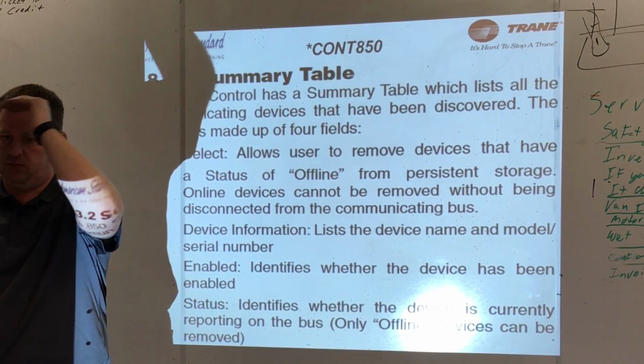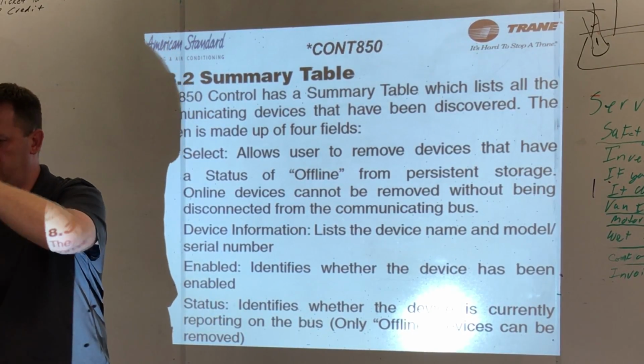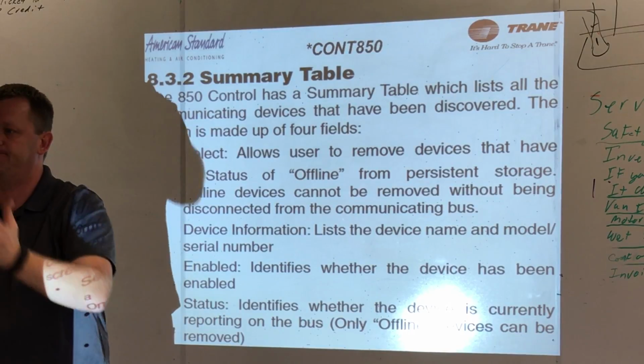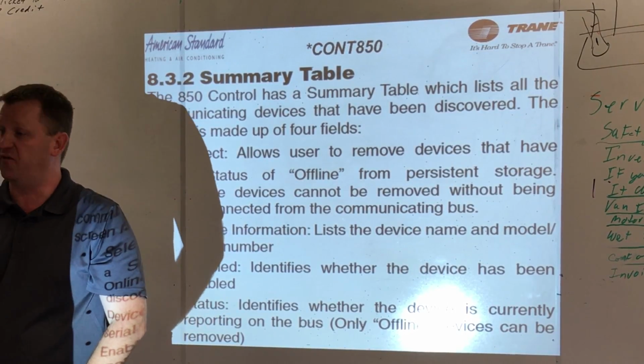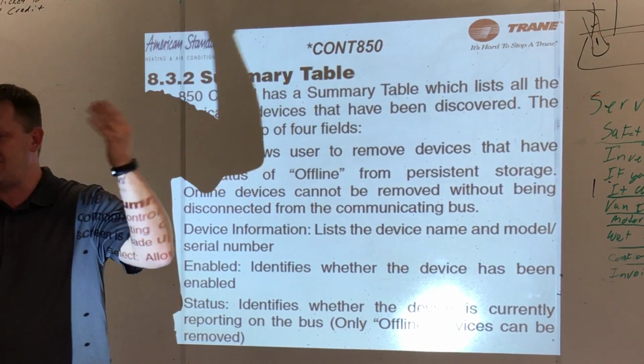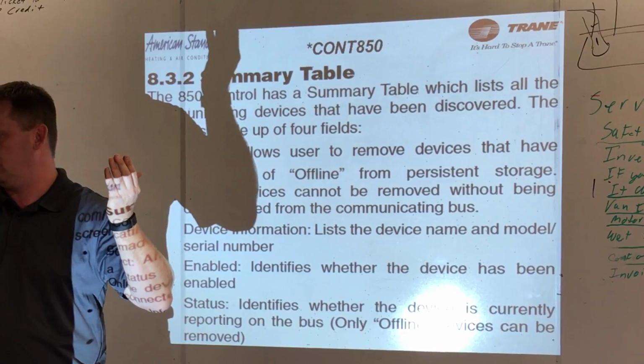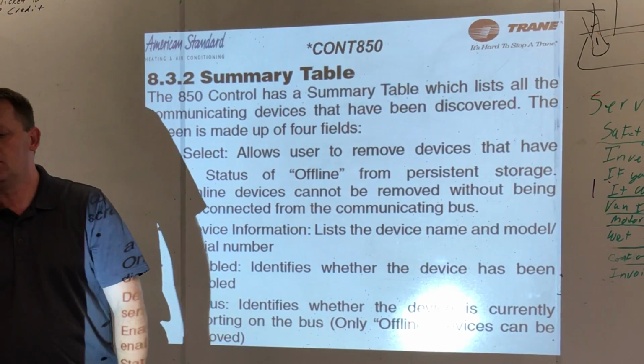Okay, you're going to go to error 126 and it's going to tell you what device is off. It'll tell you indoor unit online, outdoor unit online, Clean Effects offline. Okay, we got a problem with the Clean Effects we need to dive into, right? If they're all offline, we know there's a short somewhere in the system, or the stat can't talk to anything. Okay, so we have a stat wire issue. So that's kind of how we can dive into those.